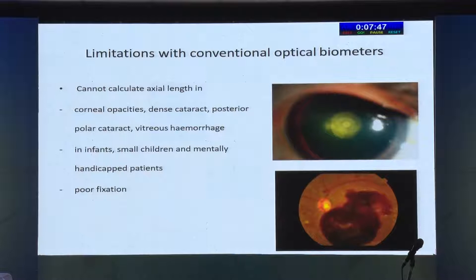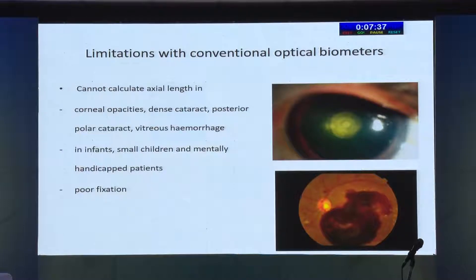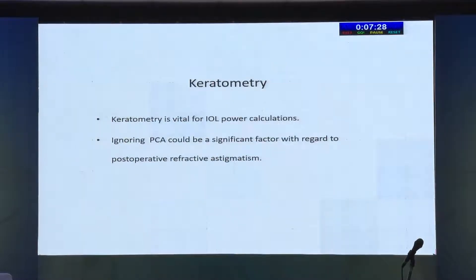The limitations — I wouldn't say they still apply. Previously, with dense cataracts, especially posterior subcapsular and dense mature cataracts, these optical biometers were not working. But with swept source, you'll be surprised — in a totally white cataract, you still get a reading, and the reading is very, very accurate.